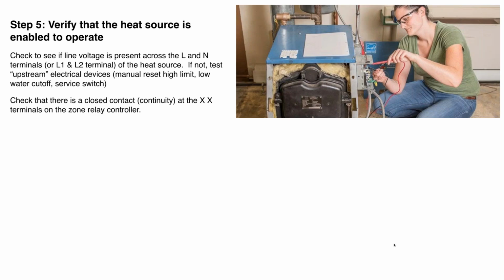Okay, check that there's a closed contact, continuity, at the XX terminals on the zone relay controller. If you're using zone relay controllers for pumps or for zone valves, typically the XX contact is an isolated contact that closes whenever any zone calls for heat. And if you have continuity across there, in other words, you put your meter on there and you have essentially zero resistance, or you set it and you get a little tone, that means that contact is closed. If you're not getting that, something is wrong with that zone relay controller or upstream of that.